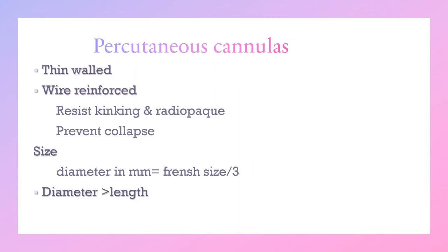Cannulas are an important part in determining ECMO flow in the circuit. They have the following characteristics: thin-walled with maximum internal diameter and the least external diameter; presence of wire reinforcement, which helps them resist kinking during insertion and also makes them radio-opaque so we can follow the insertion site by X-ray; and they prevent collapse at the venous side, which can generate minus 100 mmHg by the pump.